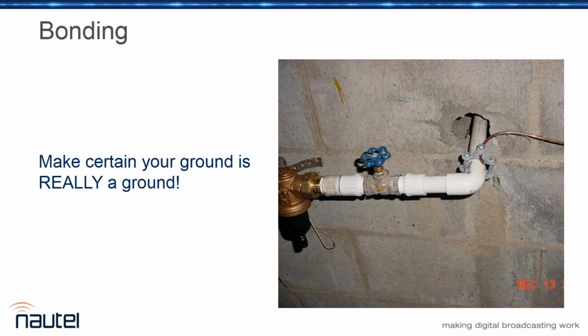The only one I don't like to see is open Delta. Oh, that's poison. Absolute poison. If you do have a 2-transformer open Delta, then you're better off configuring the transmitter to run single phase and running it across one leg. Yep. Run, do not walk for the exits if you see only 2 pole pigs on the pole.